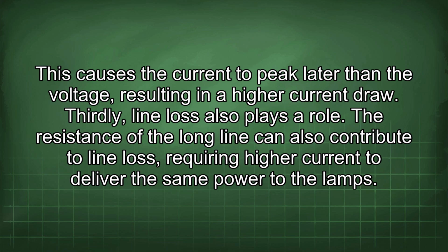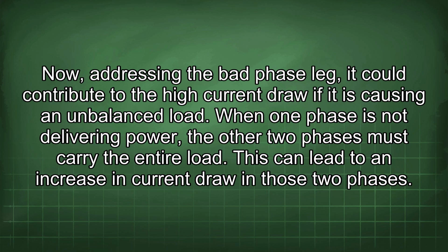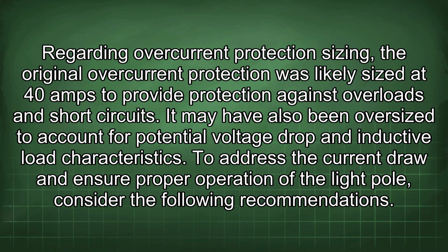Now, addressing the bad phase leg, it could contribute to the high current draw if it is causing an unbalanced load. When one phase is not delivering power, the other two phases must carry the entire load. This can lead to an increase in current draw in those two phases. Regarding overcurrent protection sizing, the original overcurrent protection was likely sized at 40 amps to provide protection against overloads and short circuits. It may have also been oversized to account for potential voltage drop and inductive load characteristics.